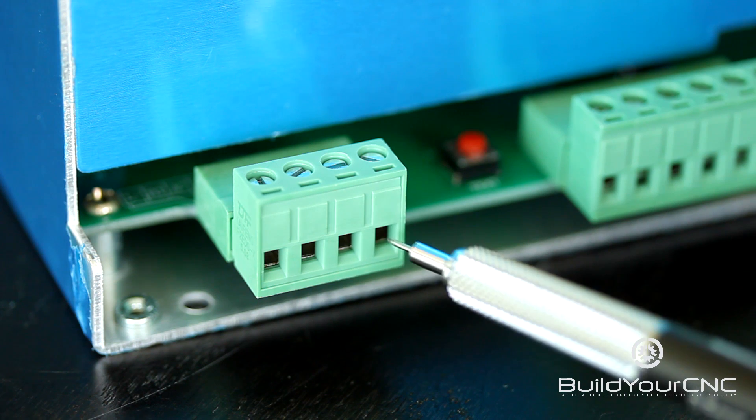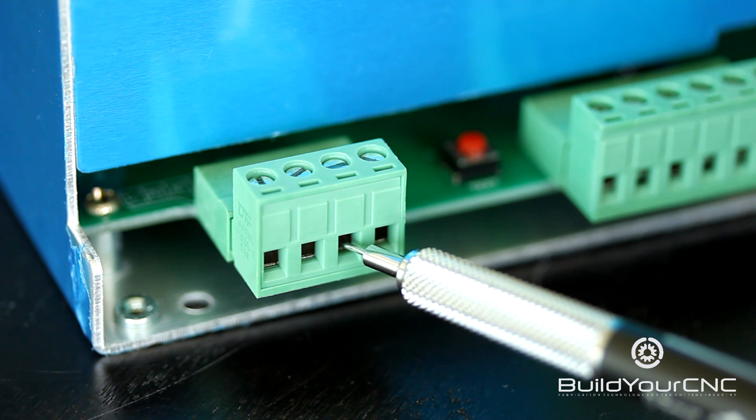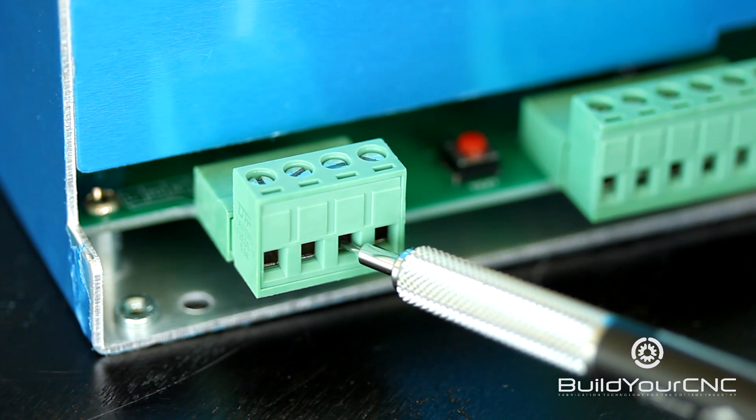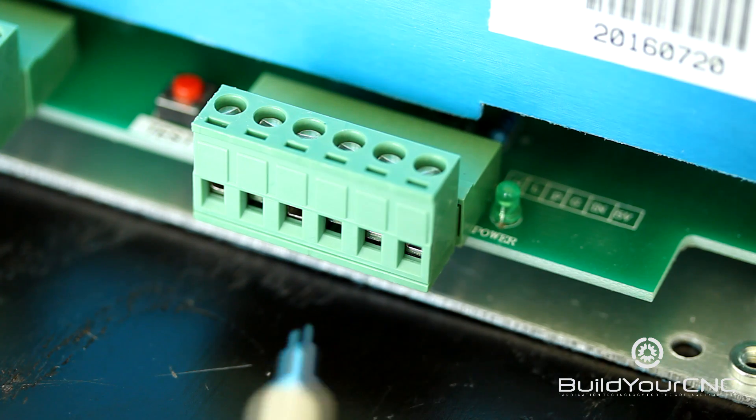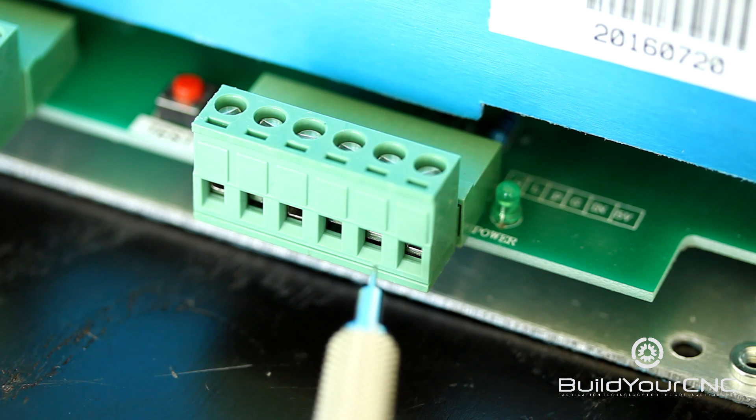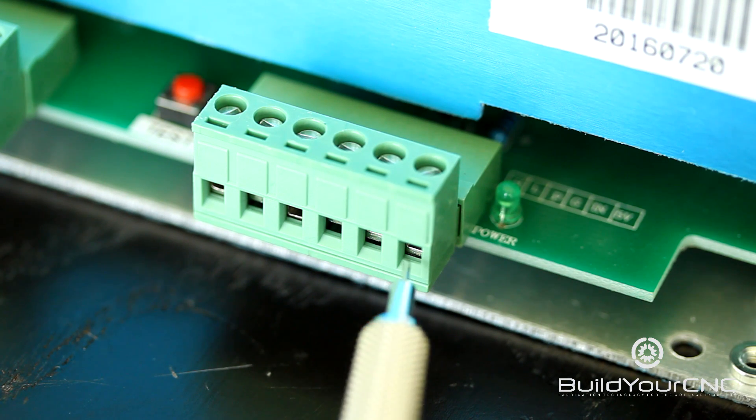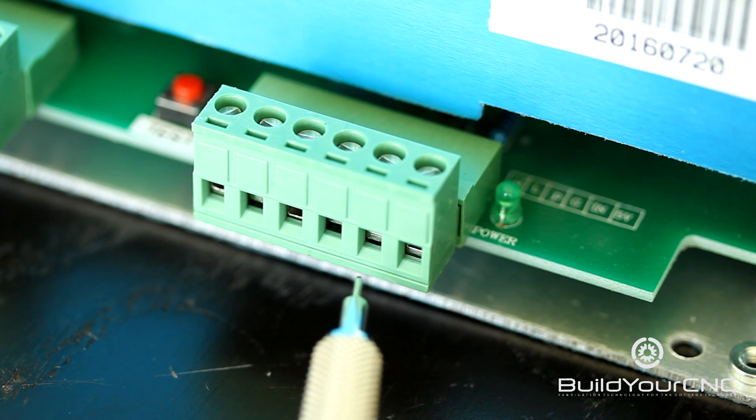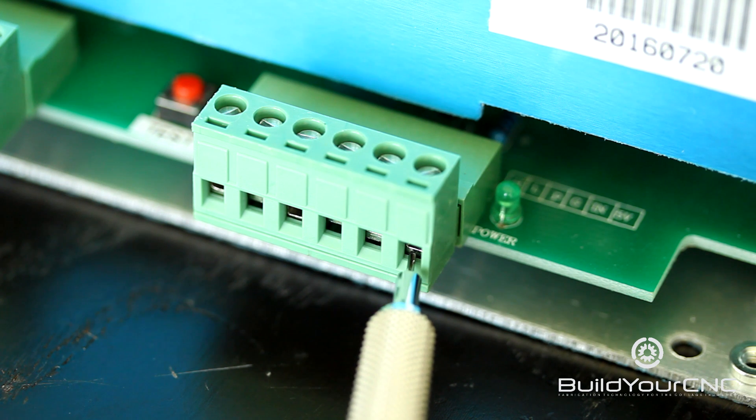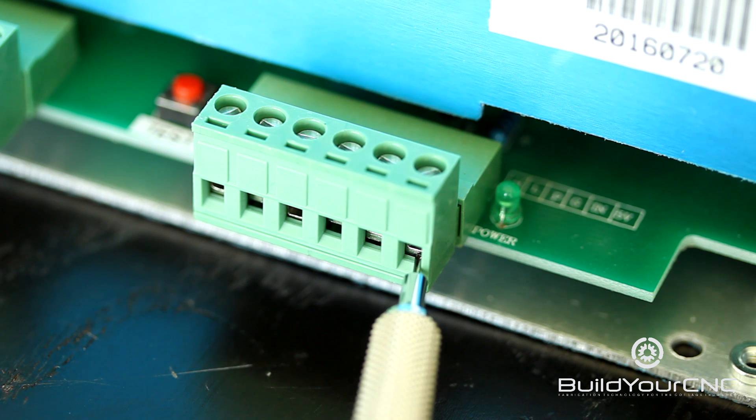The last two are for the AC neutral and live in no particular order. The second bank of terminals is the digital side that controls the power supply, which controls the laser output. The first terminal is the 5 volt input. This provides the 5 volts for digital level power.